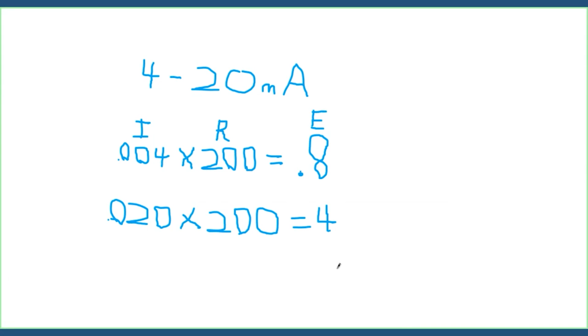So what we do is we convert a 4 milliamp signal to voltage, and the voltage reading is 0.8. So at 4 milliamps, we should be seeing 0.8 volts. Likewise, if we're at full range on that pressure transducer and we're getting 20 milliamps, we're doing the same conversion, and the answer is 4 volts. So if I have a pressure transducer that's 0 to 100 psi and it's a 4 to 20 milliamp pressure transducer, my voltage range is 0.8 to 4 volts. So 0 pressure equals 0.8 volts, and 100 psi would equal 4 volts.